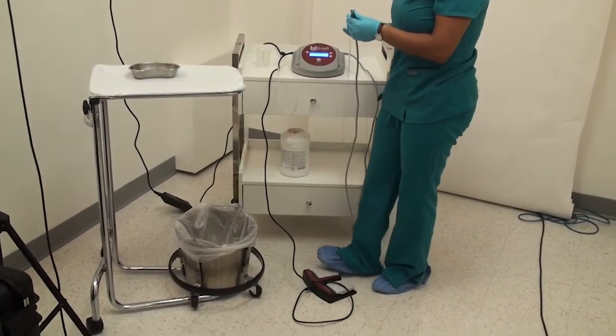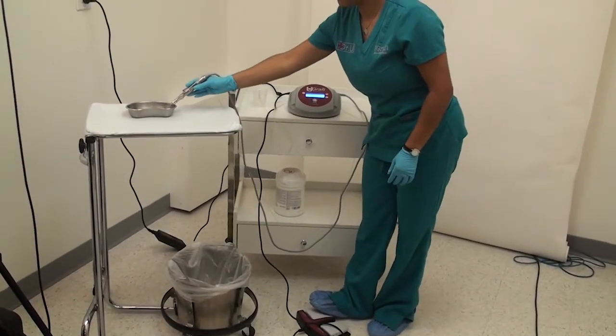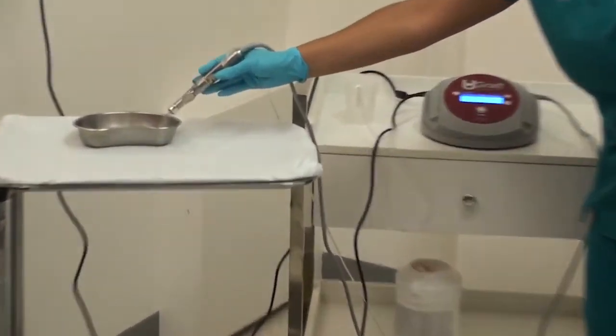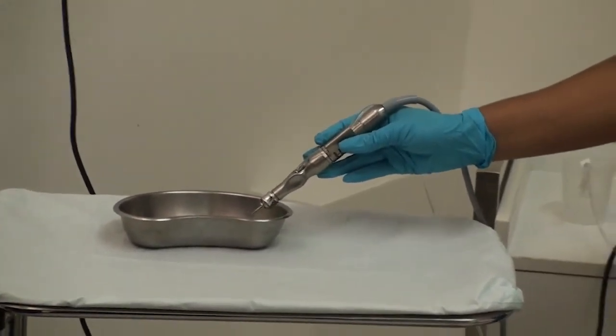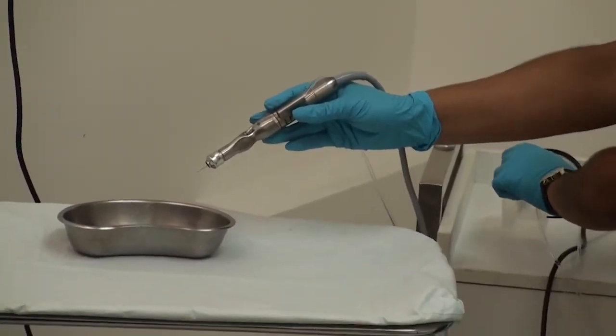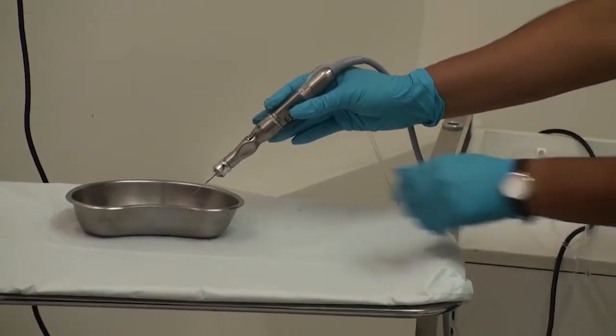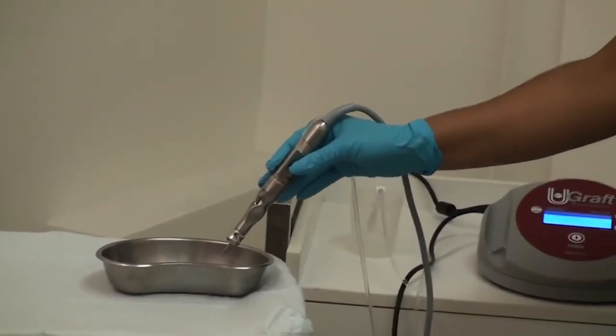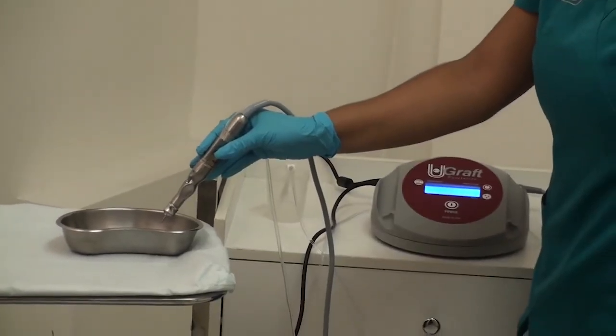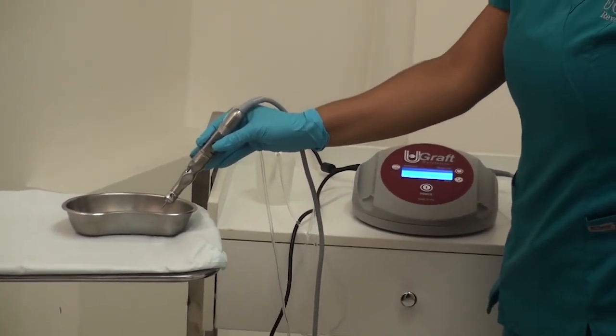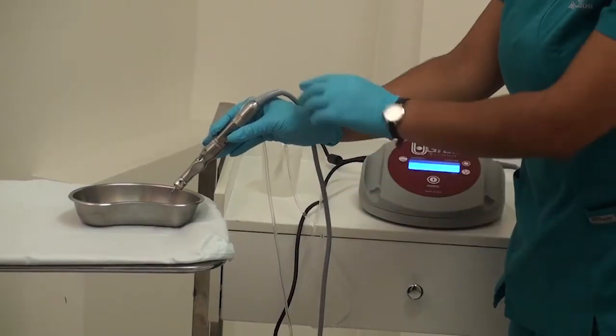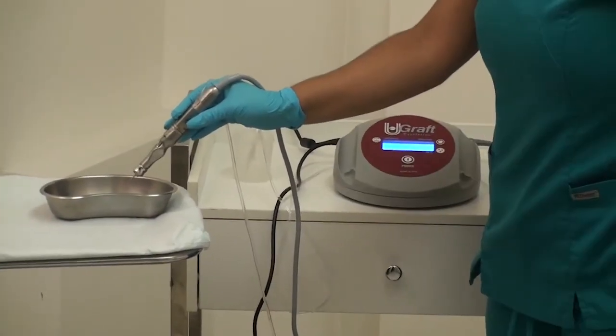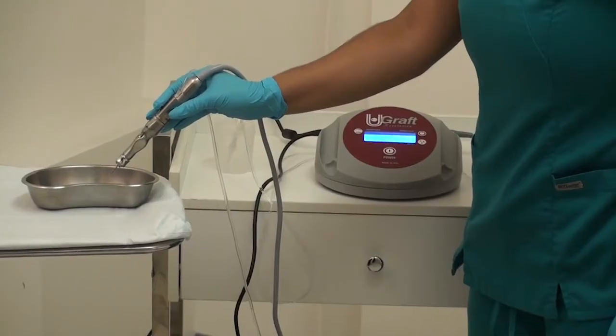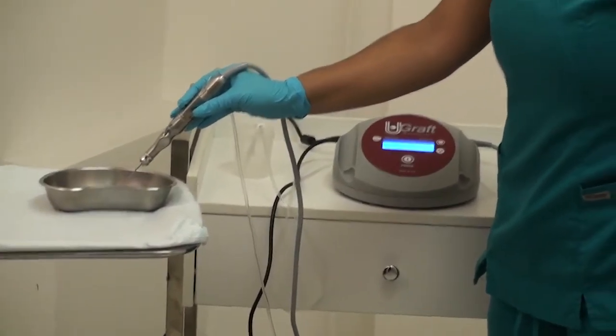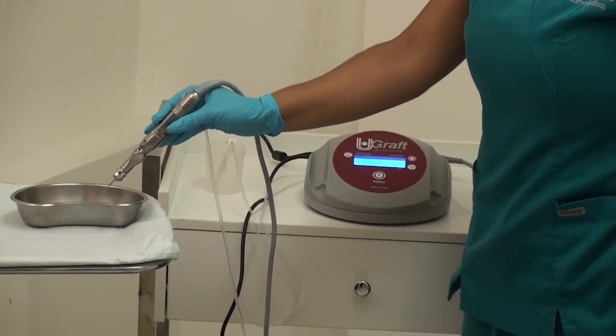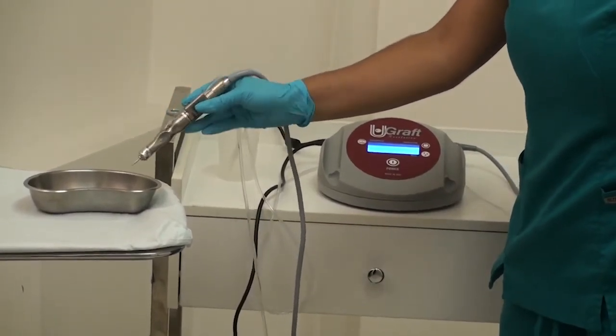Then, by pressing the right foot pedal, flush your 2 ounces of distilled water into a receptacle of choice as shown. You want to exhaust the entire 2 ounces of distilled water, which is what it would take to optimally flush and rinse the internal parts of the handpiece of the saltiness of the physiologic fluid. Salt has a corrosive effect on the internal parts of the handpiece. The use of distilled water helps flush the salt water out of the system. It takes 2 ounces of water and probably just about 1 minute to accomplish this task.